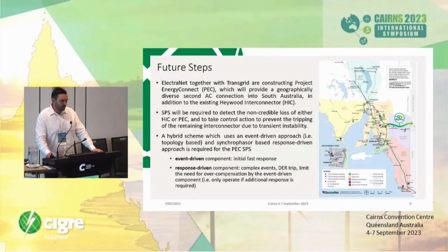The next step, so the scheme is evolving. This isn't the end. There's currently a second AC interconnector that's going in, Project Energy Connect, so Electranet working with Transgrid, building a double circuit interconnector, and the scheme will evolve to take that interconnector into account, and this special protection scheme will then be required to detect the non-credible loss of either the Heywood interconnector or the PEC.